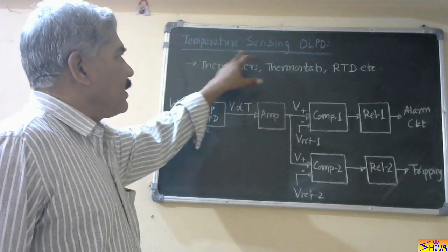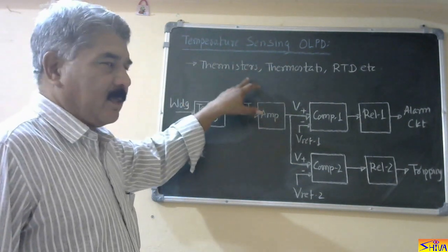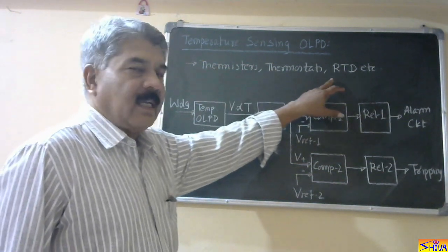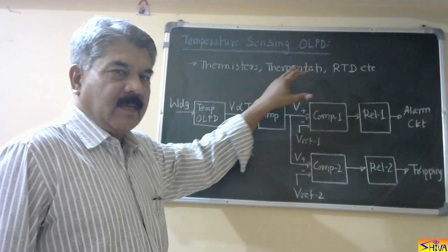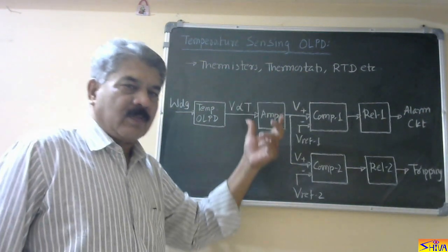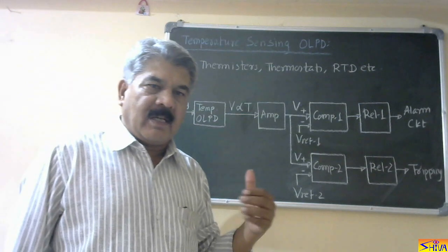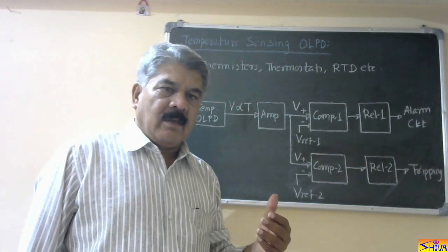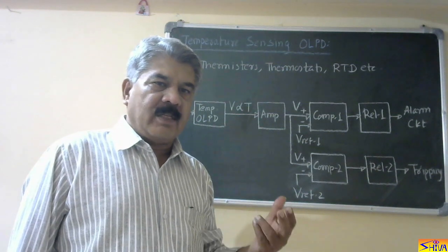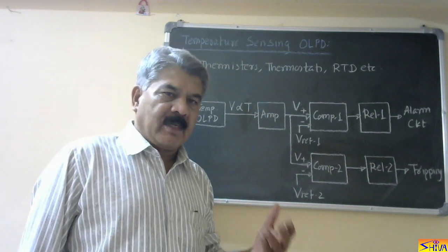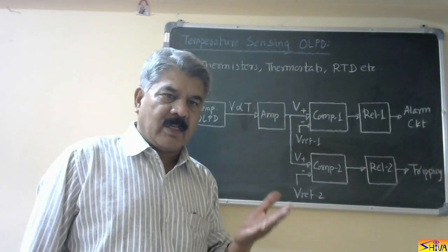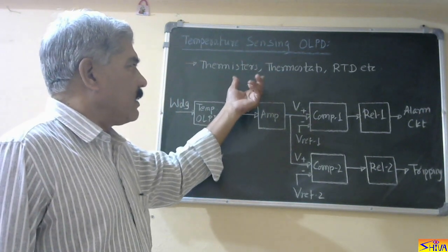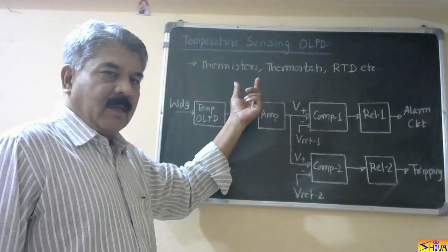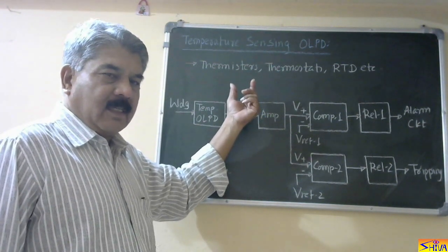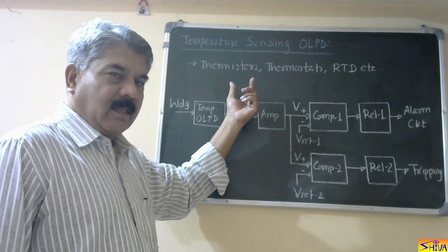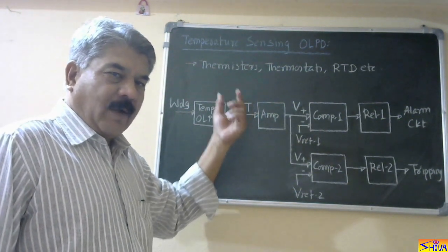Now when we say temperature sensing overload protective device, it can be thermistors, thermostats, or RTD. RTD means resistance temperature detector. Now these are basically transducers which convert temperature into voltage. Their input is temperature and output is voltage. Voltage proportional to temperature. As temperature increases, the voltage also increases. So these devices are very small. They are embedded in the machines, in the motors, and they are connected directly. They are placed on the winding. So winding temperature they sense.